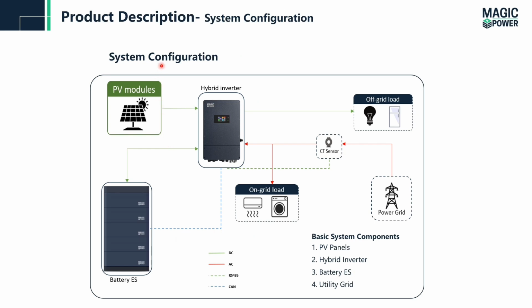The next one is system configuration. Basically, the system has four basic components. The first one is the PV, the hybrid inverter, the battery energy storage system, and the utility grid. So we connect some loads to the system, which are off-grid if connected to the inverter. If the load is directly connected to the grid, that's an on-grid load. So there is no concern of the inverter or the energy storage system with on-grid loads. It will only be responsible for off-grid loads.